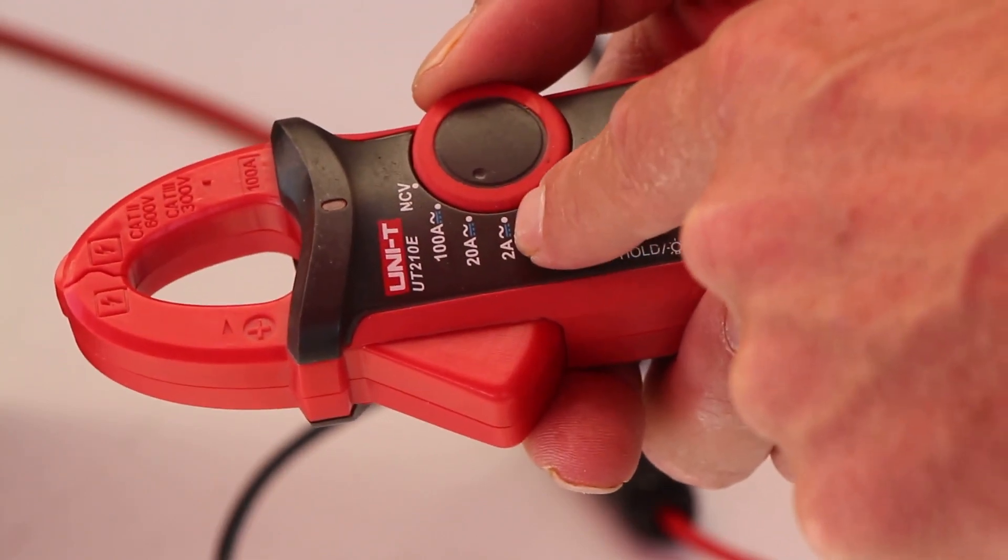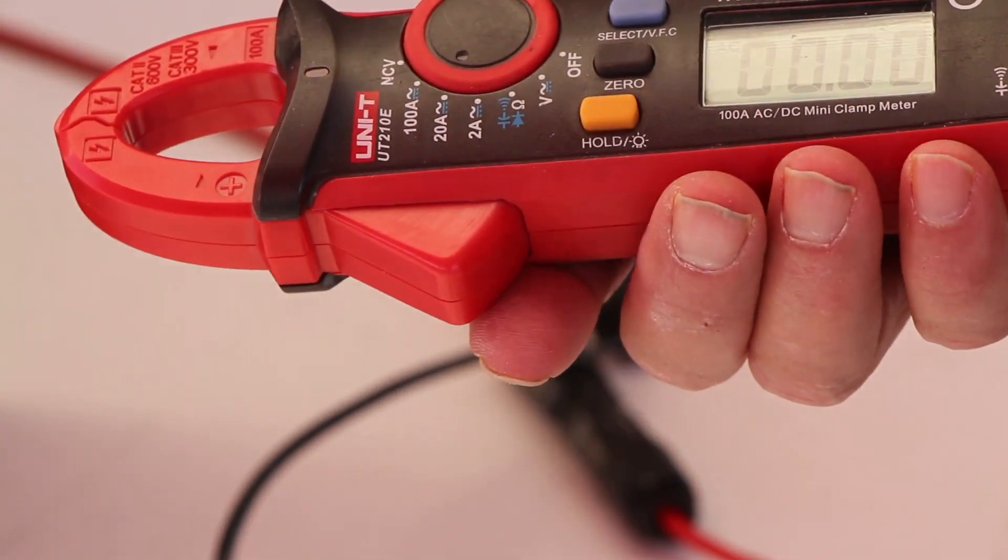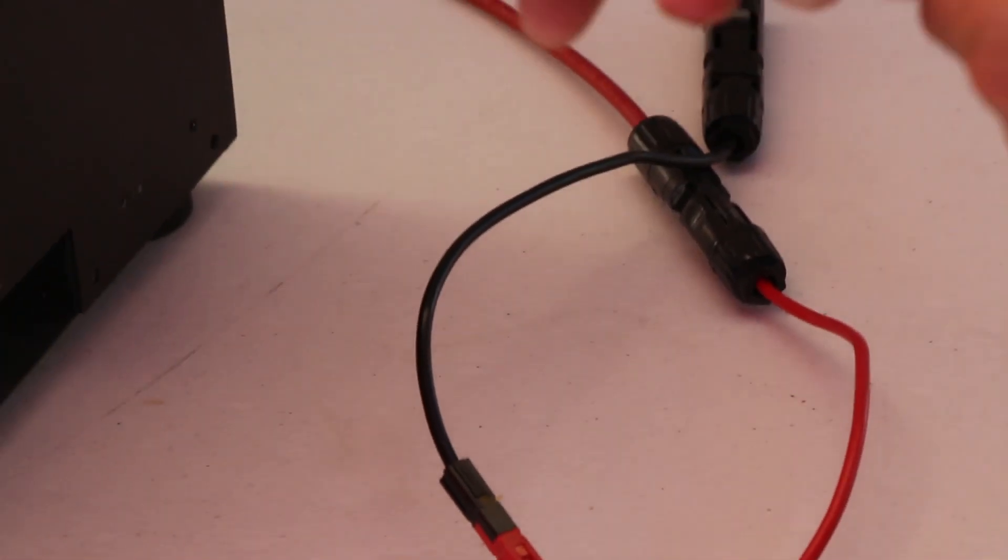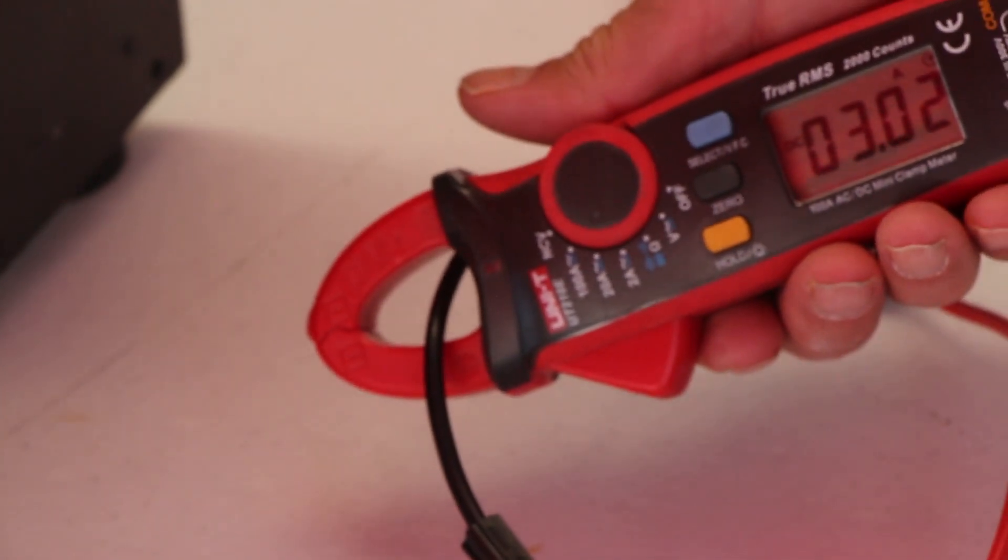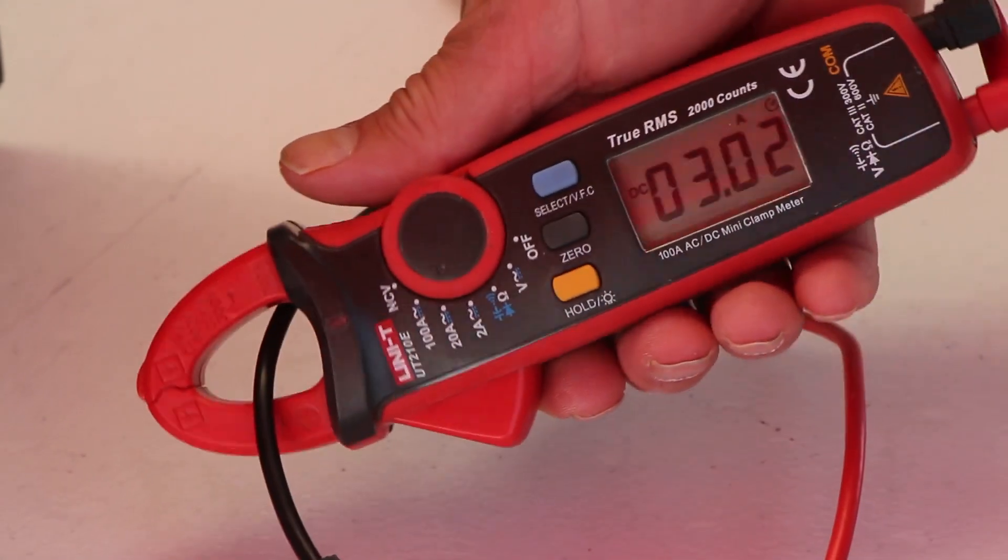We want to be over that 5 amps, so 2 amps would be too low. So we turn it to 20 amps and then we push the select because we got to go to DC again, and then you simply clamp this over that line. Okay, so we are putting out 3 amps.